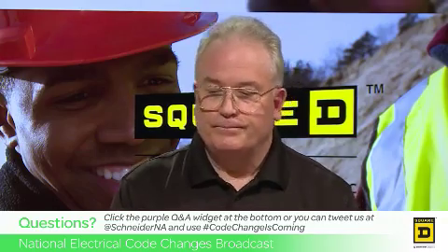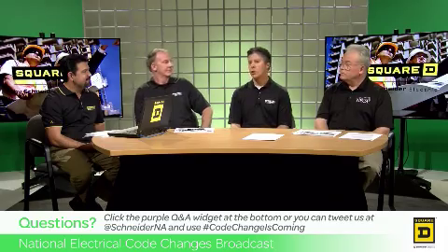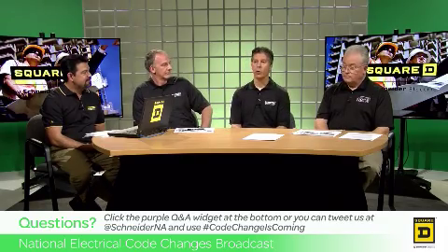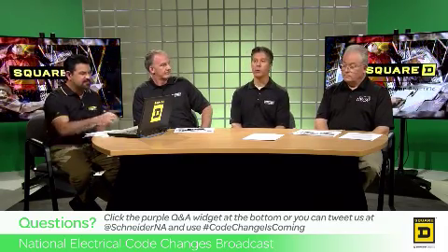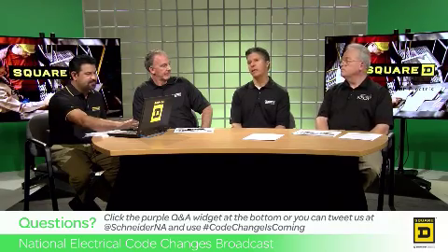Absolutely. Here's a general question, but it's around primary injection. Can testing ground fault and trip with primary injection be done at the factory on the entire assembly? When we have a complicated equipment lineup with multiple sources, then certainly that testing is done at the factory to assume that all the ground fault system and parameters work as designed. But the NEC is very clear that the final test is done at the installation. So it has to be done on site.